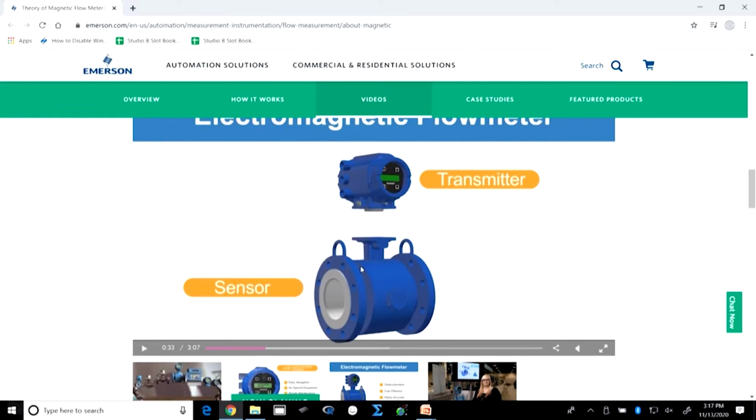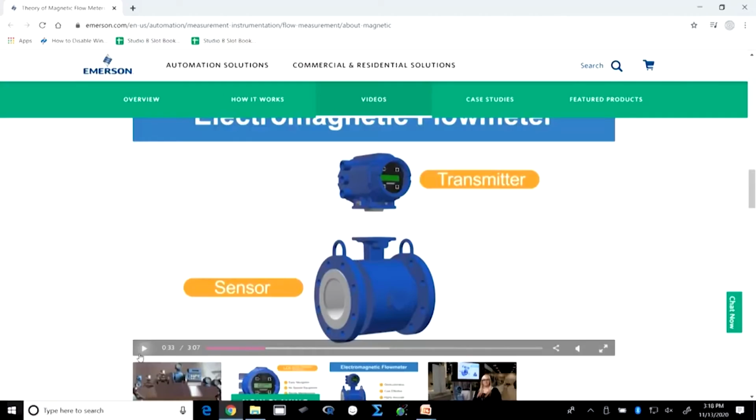So, magnetic flow meters typically do not require as much distance before and after, certainly not after, and they can be done inline in pipes and such. That is why we saw earlier that in the rising mains too, you can have these magnetic flow meters. Let us see what this is about. We have a transmitter and a sensor, but what is it that we are transmitting and what is the principle? Let me see if I can keep up with the video.